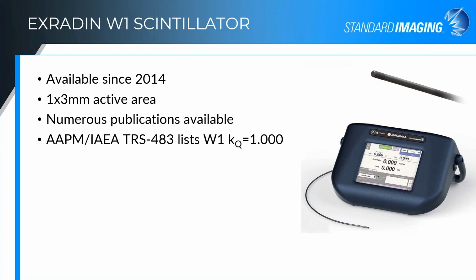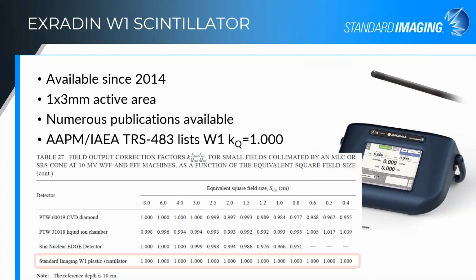One of my favorites is that joint publication on small field dosimetry from the AAPM and the IAEA, Technical Report Series 483, which lists the W1 KQs in a number of tables. And for every table that it shows up in, correction factors are unity for every field size. And this, again, really is a reflection of the fact that this detector is water equivalent. We're not seeing energy dependencies as that field size changes, as the source is occluded, as the scattering energy changes or anything like that. It does not require that correction for the changing energy with the change of field size in small field measurements.